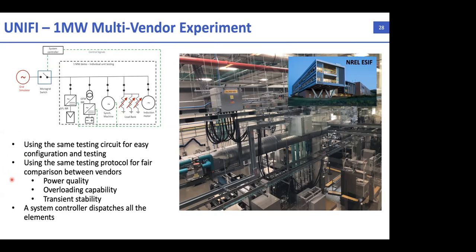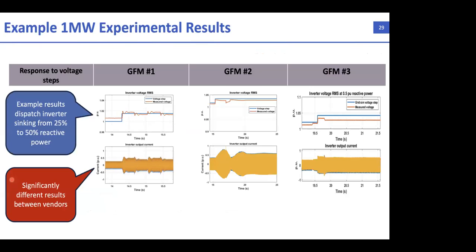One interesting thing we've seen is that different grid forming technologies can be developed and deployed, but they can come up with different ways of evaluating a specification. For example, if we ask it to do a specific voltage or power step, we can see different response characteristics in the output current from three various manufacturers. What we're interested in isn't necessarily the overall performance of individual units, but how to ensure their performance meets the specifications in the grid forming specifications documents.